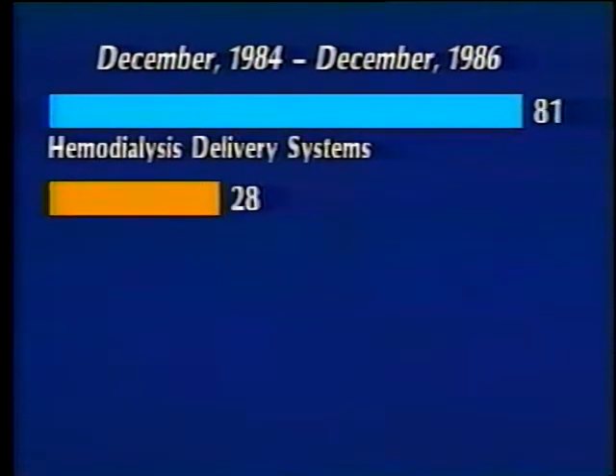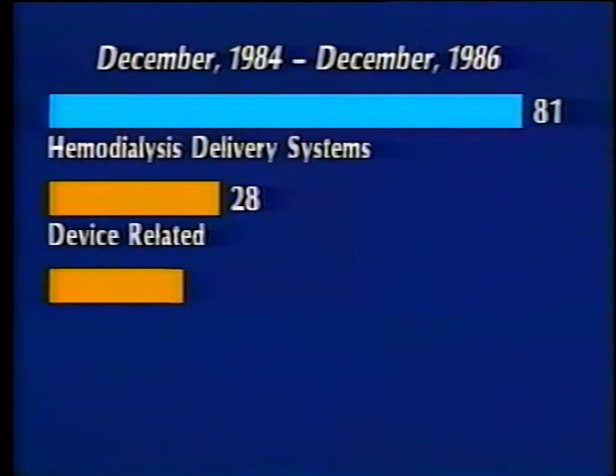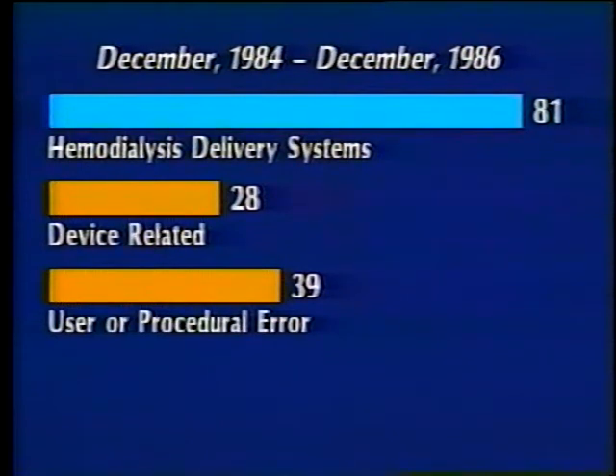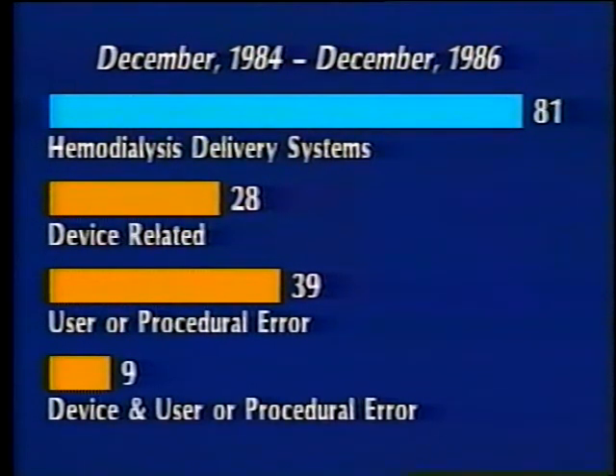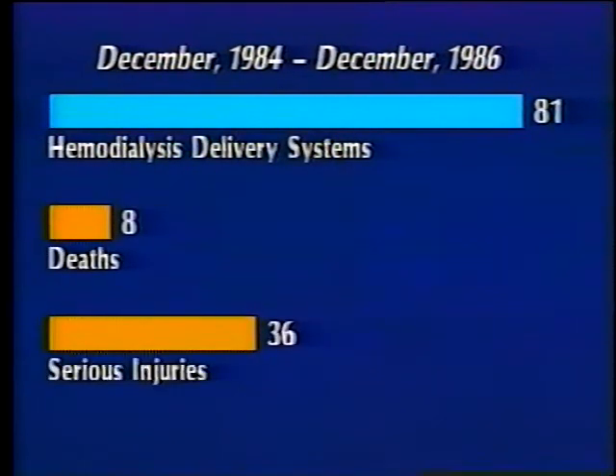Take the last 2 years of MDR reporting, for example. Of the 81 reports we analyzed that involved hemodialysis delivery systems, 28 of these incidents were determined to be device-related, 39 were attributed to user or procedural error, and 9 were a combination of device and user or procedural error. These 81 reports also included 8 deaths and 36 serious injuries. The FDA certainly can't regulate user or procedural problems, the human factor. Our role, as defined by the Food, Drug, and Cosmetics Act, is to assure the safety and efficacy of the device.